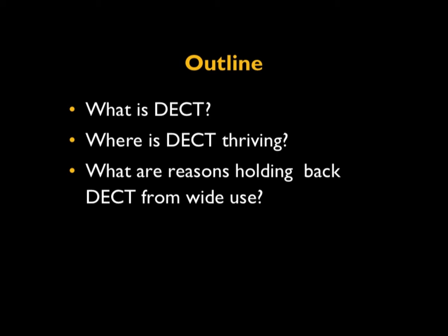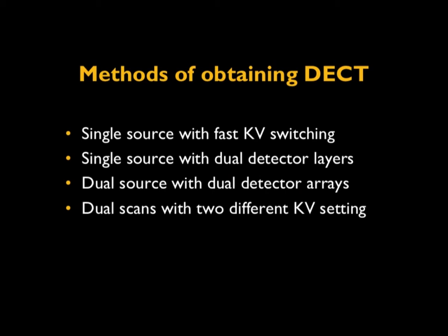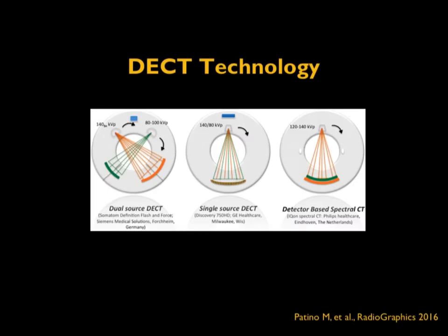Dual energy CT is often called spectral CT. It involves the generation of two x-ray photon spectra, though the method varies among CT manufacturers. There are currently four methods of obtaining dual energy CT: single source with fast tube voltage switching (kV switching), single source with dual detector layers, dual source with dual detector arrays, and dual scans with two different kV settings.